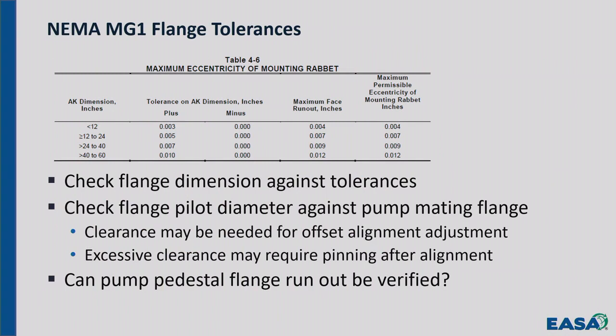These are the NEMA tolerances for flange runout. Size of the flange, the dimensional tolerances, so up to 3 thousandths over, 5 thousandths, up to 10 thousandths over. That's the amount that the ID of the flange or OD of the flange is larger than the spec. And this is the face runout and the eccentricity. Okay? So there's tolerances for those that you should at least meet the NEMA standards. Okay? And you want to know how that matches up against the pump flange.